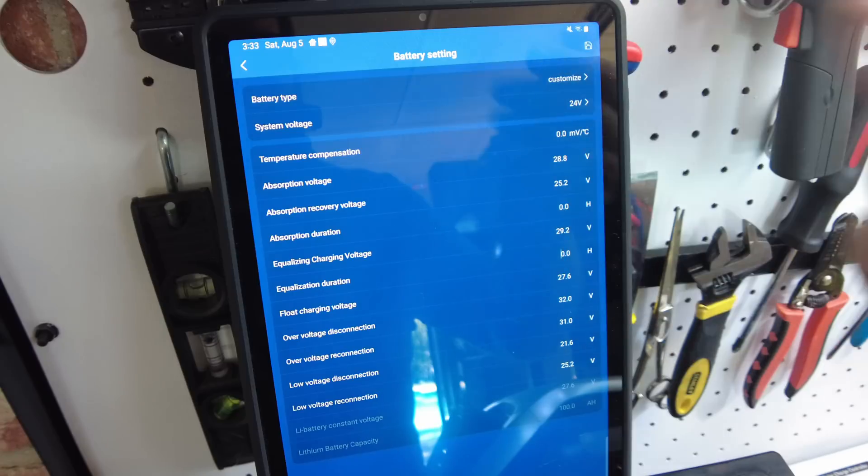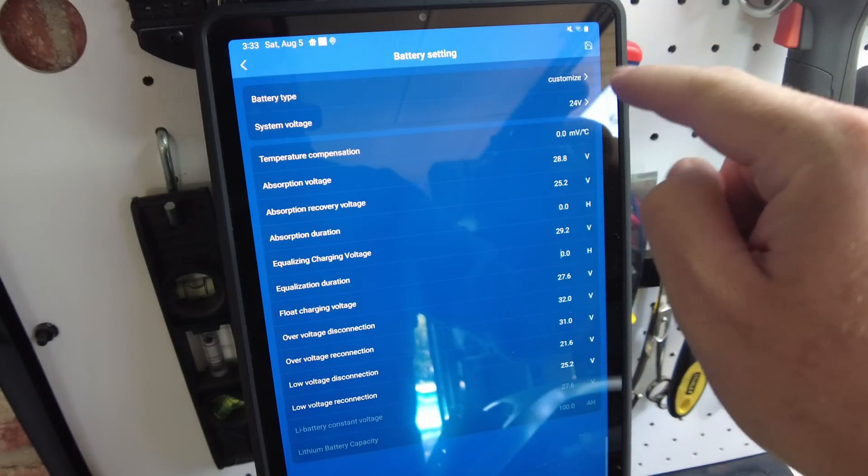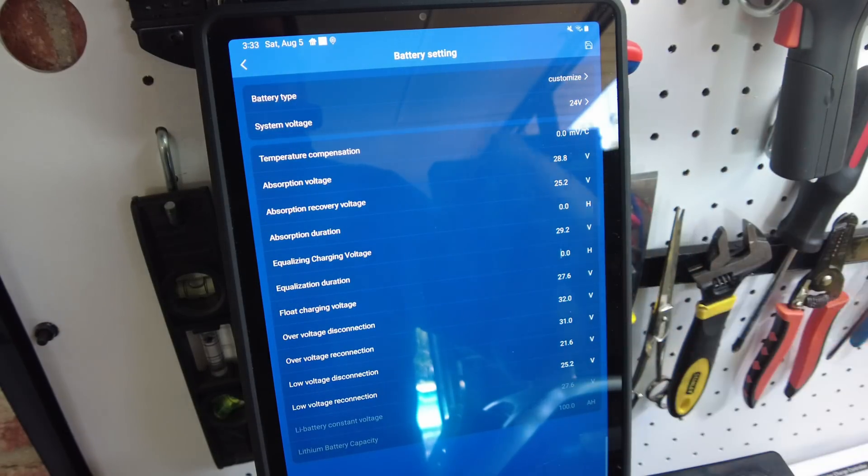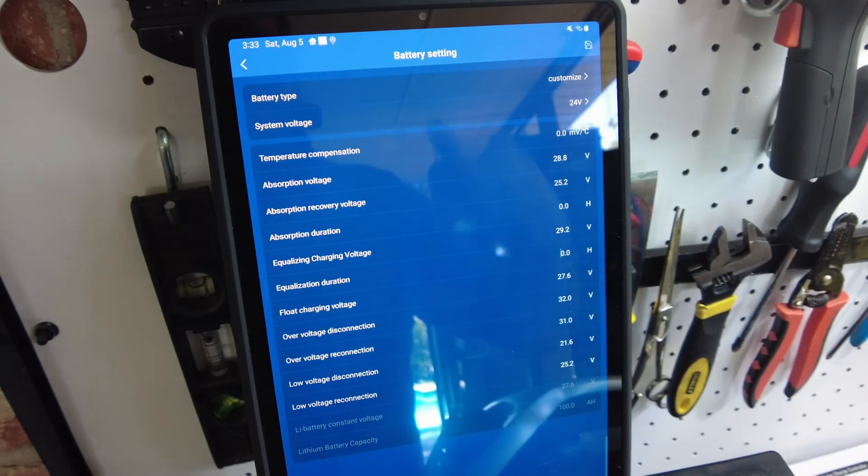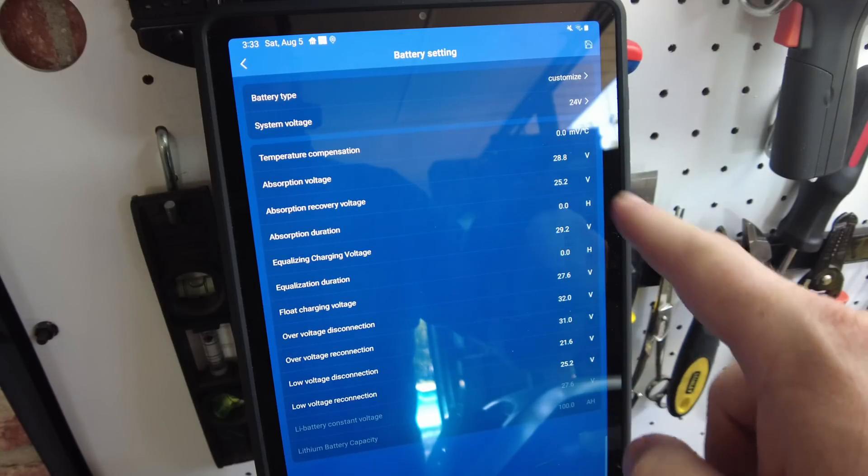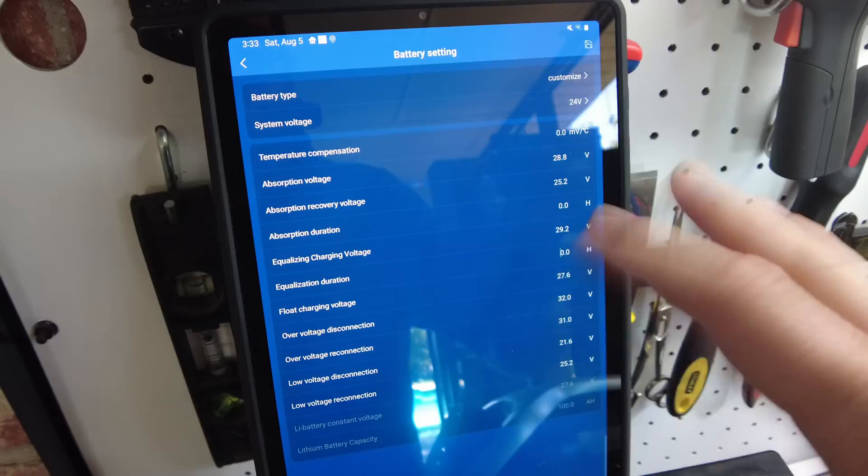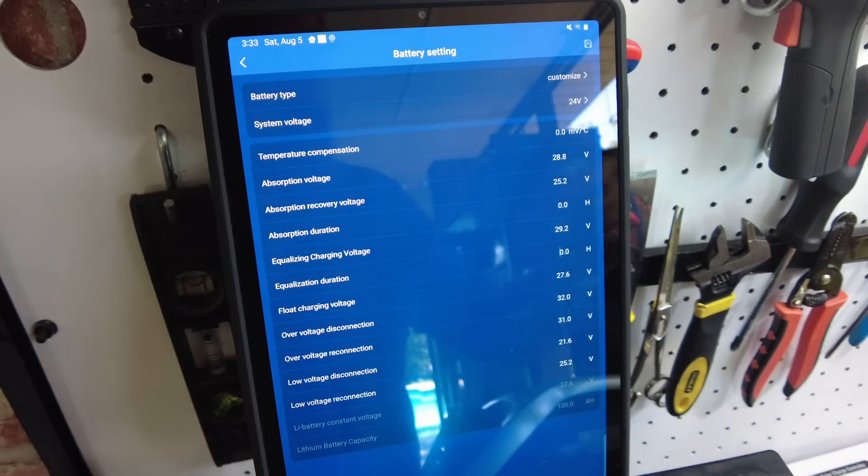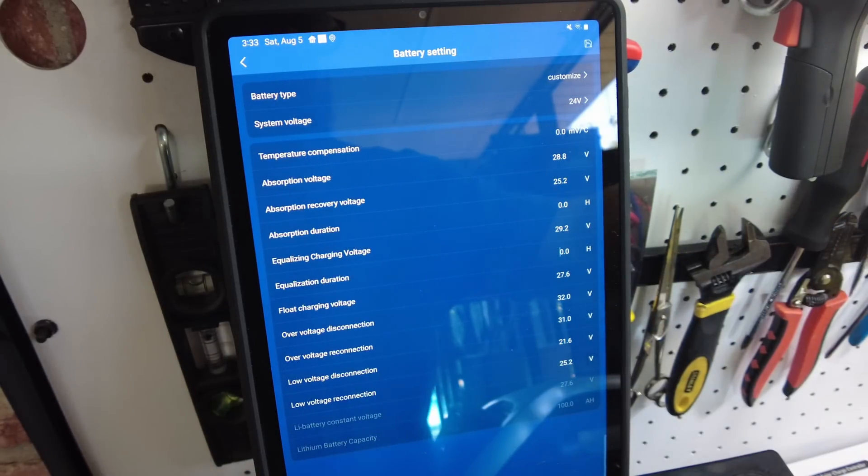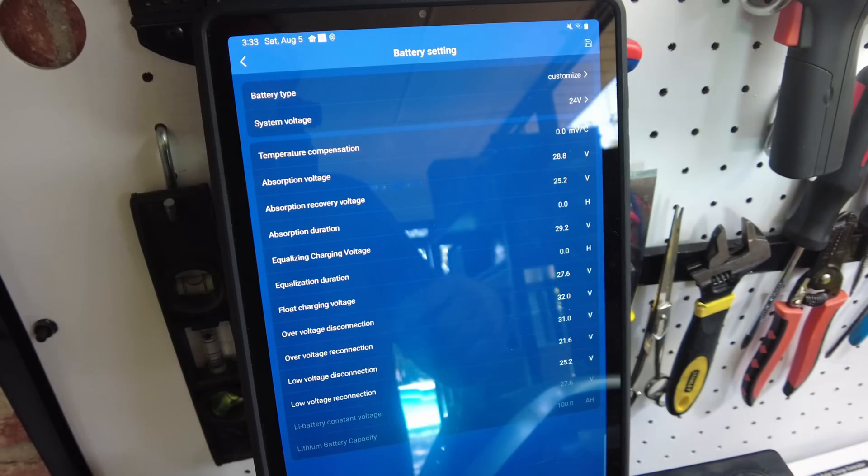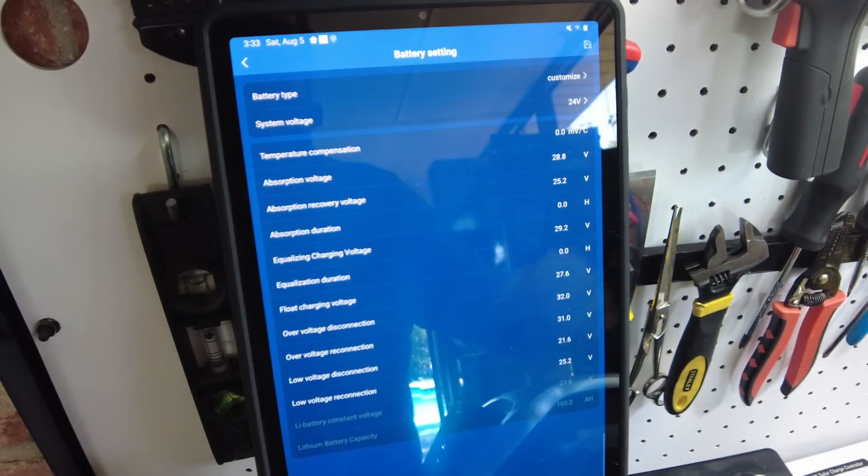And then when you place a load on it, the load will drain power out of your battery. And then after some period of time, the charger will come back on and charge your battery back up. So you're constantly draining power out of your battery and charging your battery back up, draining power out, charging it back up. Whereas if you use this customized setting, it actually will detect the load if your battery is full and only provide enough power for the load like it should.